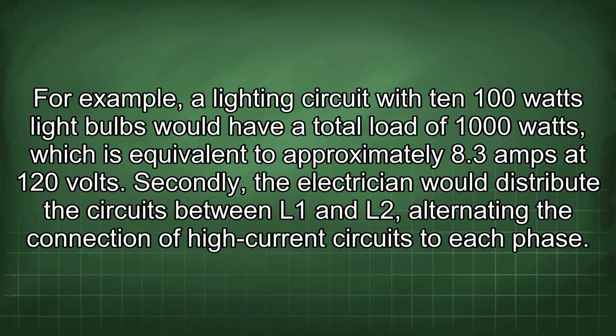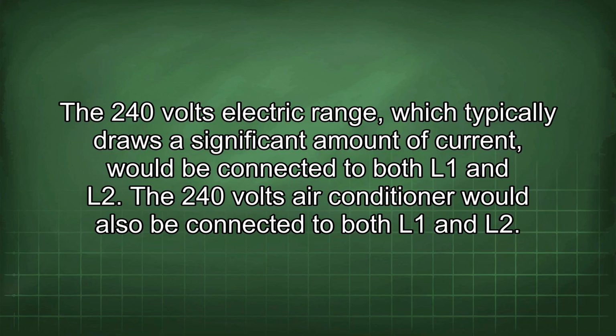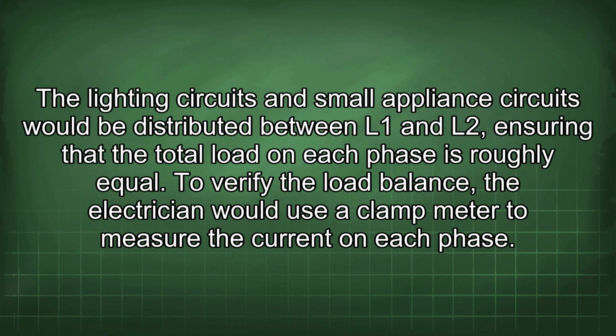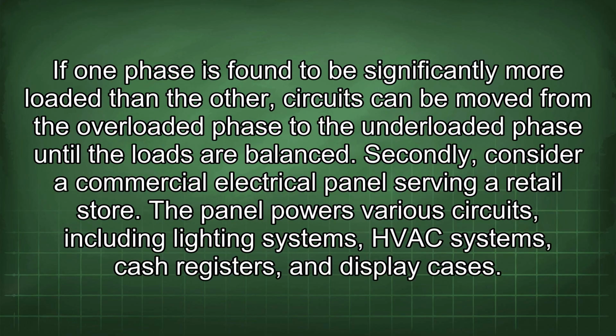Secondly, the electrician would distribute the circuits between L1 and L2, alternating the connection of high current circuits to each phase. The 240 volts electric range, which typically draws a significant amount of current, would be connected to both L1 and L2. The 240 volts air conditioner would also be connected to both L1 and L2. The lighting circuits and small appliance circuits would be distributed between L1 and L2, ensuring that the total load on each phase is roughly equal. To verify the load balance, the electrician would use a clamp meter to measure the current on each phase. If one phase is found to be significantly more loaded than the other, circuits can be moved from the overloaded phase to the underloaded phase until the loads are balanced.